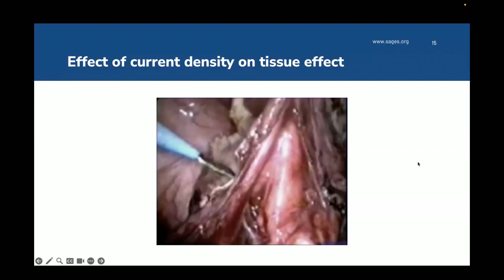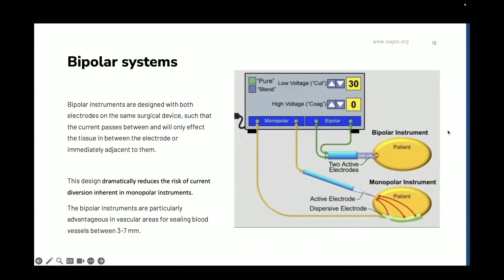Contrast this to a bipolar system where the only part of the patient that is affected by the current is the part between the two active electrodes. So this can lead to less current diversion, but you don't have as much flexibility. This is typically used when sealing vessels, and it can be very effective in sealing vessels 3 to 7 millimeters wide.